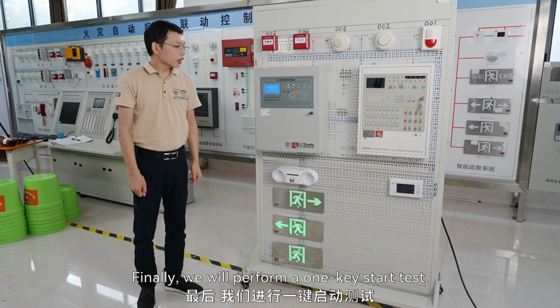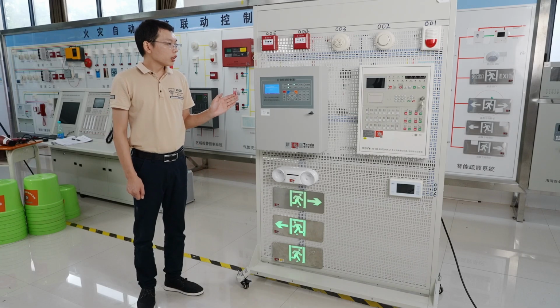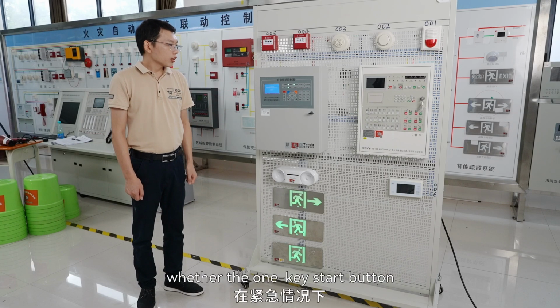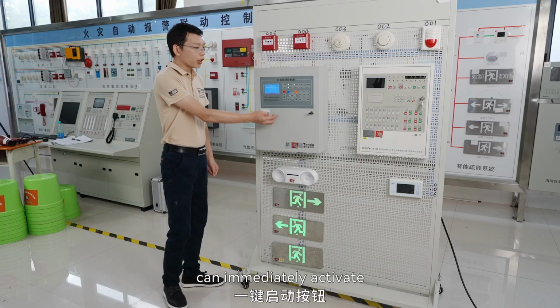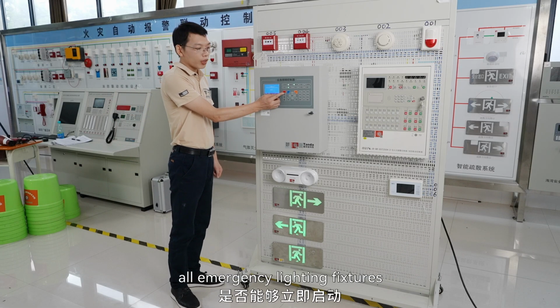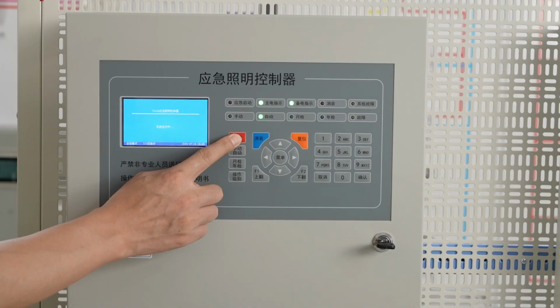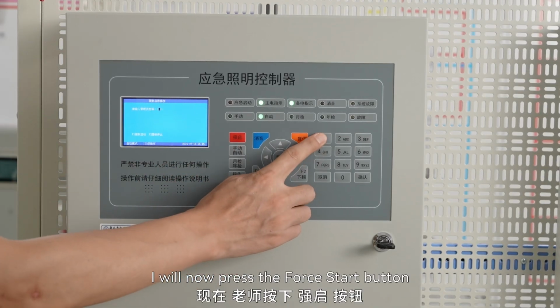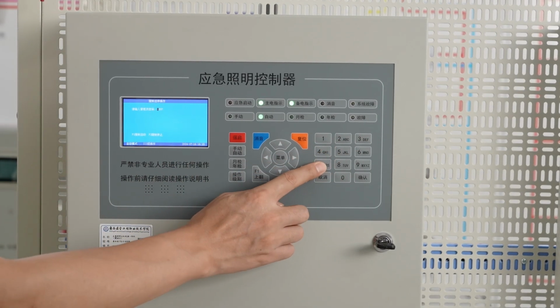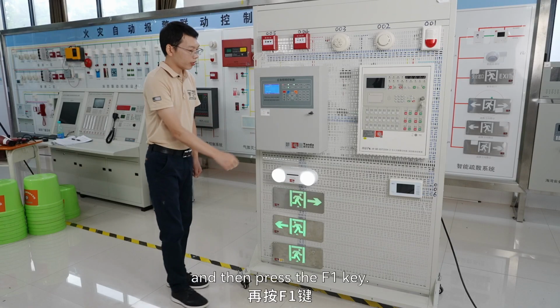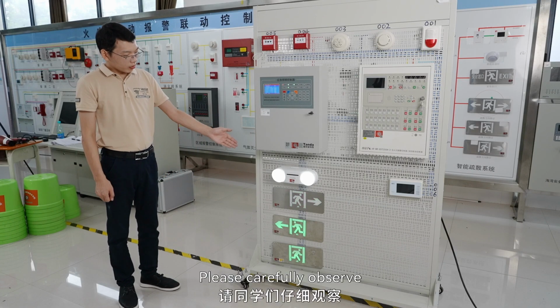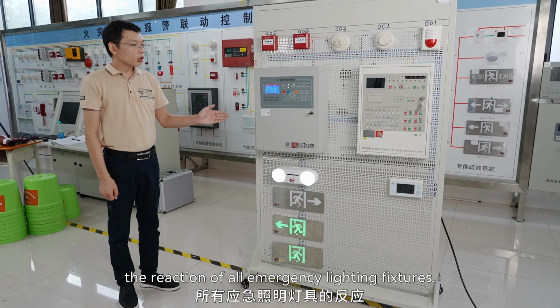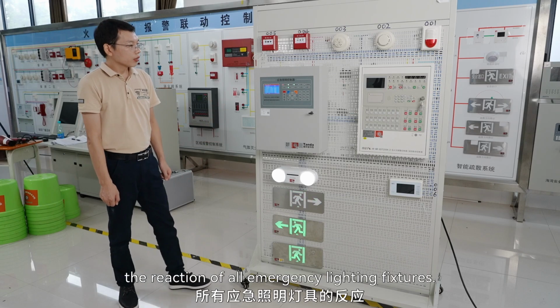Finally, we will perform a one-key start test. This test aims to verify whether the one-key start button can immediately activate all emergency lighting fixtures in an emergency. I will now press the force start button and then press the F1 key. Please carefully observe the reaction of all emergency lighting fixtures.